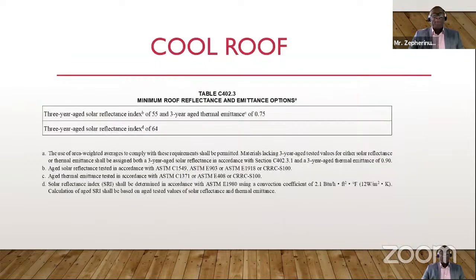and ensure that it is a cool roof. Now, for residential and commercial buildings, this requirement, the minimum roof reflectance and the emittance options, you will see that it is found in section C402.3 of the code. And what it speaks to is that there is a 3-year aged solar reflectance index of 55 and a 3-year aged thermal emittance of 0.75. This is what you need to be able to get from the suppliers to demonstrate that you are meeting the requirements of the code. So once again, suppliers must be in tune with what's going on, and the products that are being made available to us in the region should be able to meet the requirements or exceed the requirements of the code.